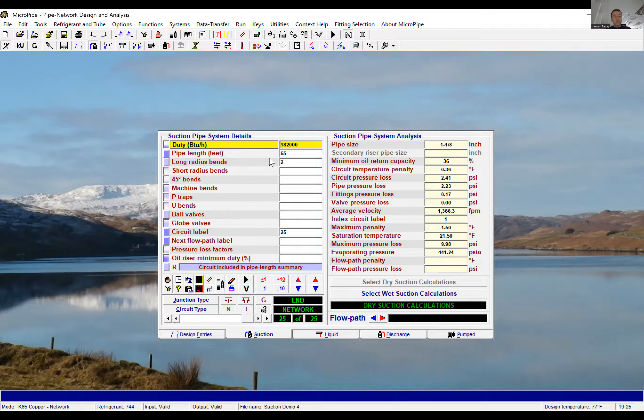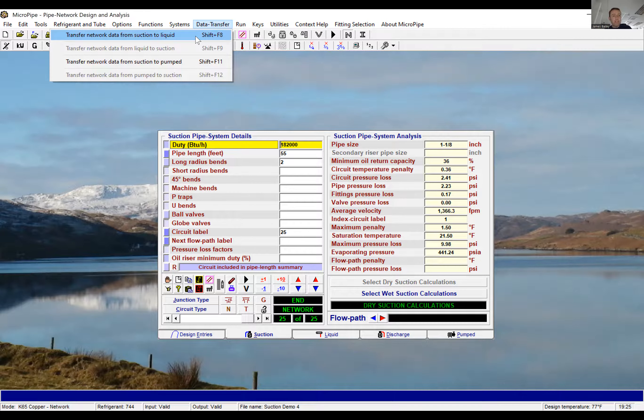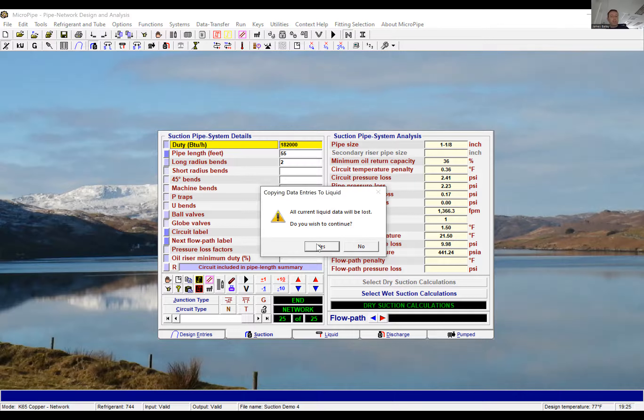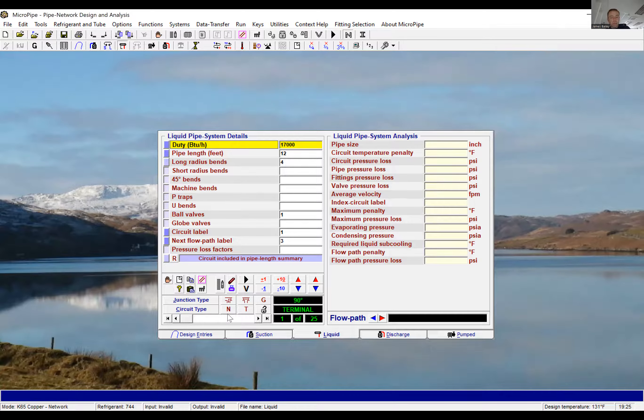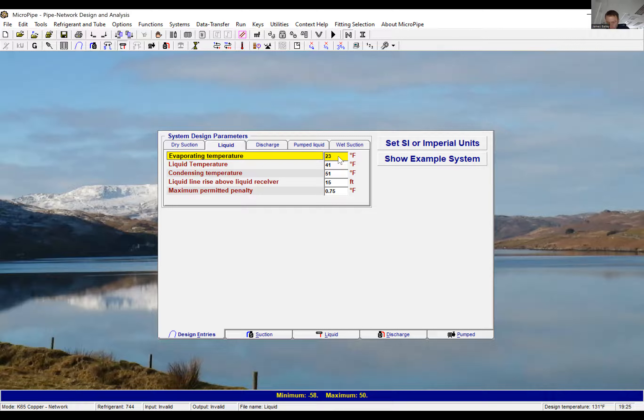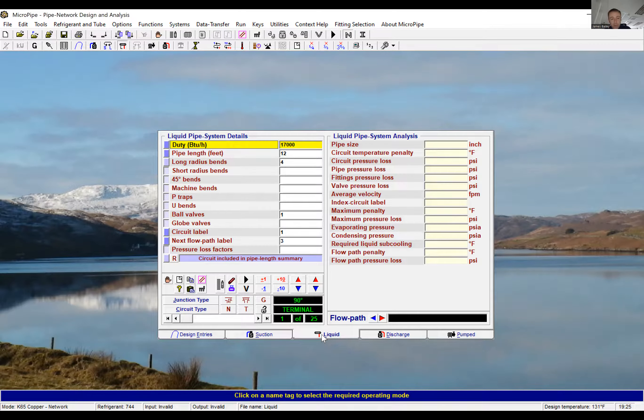Now we need to transfer the suction pipework into the liquid. What it's going to do is grab all 25 circuits and all the pipework lengths, and convert it to a liquid line calculation. Go to the top: Data-Transfer > Transfer network data from suction to liquid. Clicking on the liquid tab, we've now got 25 circuits — all blank. Let's go to those design entries, check them out. I'm happy with those. And this is where MicroPipe gets pretty awesome — hit the button and we've calculated all 25 liquid lines, just like that.